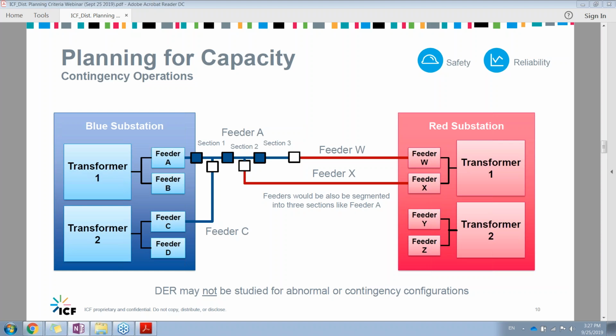The adjacent feeders in this case are feeder C connected to one section, feeder W to another section, and feeder X to another section. So we've introduced another substation source here, which is fairly common. These substations out in the real world might be a mile or two apart, and they'll have feeders that look very much like feeder A.